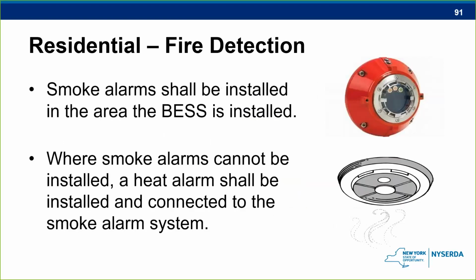And finally, whenever these systems are located indoors, they need to have a fire alarm. Cabinets that are placed outdoors might not be able to meet the requirement of smoke detectors because the air moves the smoke far away from them. So they could satisfy that requirement by using a heat detector.